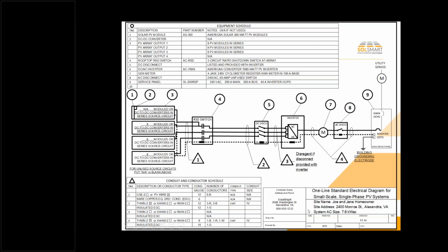Once we get to the inverter, since we have a 40 amp circuit breaker over here, this is a 40 amp circuit breaker and a 200 amp panel. So the reason 7600 watts is the magic number is that's the largest inverter that you can run into a 40 amp circuit breaker. And that 40 amp circuit breaker is the largest circuit breaker you can put on a 200 amp panel and meet the requirements of Article 705 for the 120% option for how we would connect into a house. And that 120% option is by far the most common and simplest option in the code. It's just a matter of essentially installing a circuit breaker and mounting right to it. Any other method is going to be more difficult and more complicated, both physically and cost-wise.